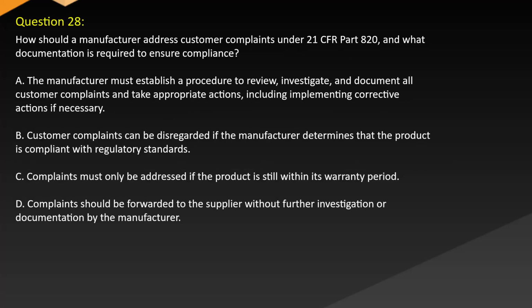Question 28. How should a manufacturer address customer complaints under 21 CFR Part 820, and what documentation is required to ensure compliance? A. The manufacturer must establish a procedure to review, investigate, and document all customer complaints and take appropriate actions, including implementing corrective actions if necessary. B. Customer complaints can be disregarded if the manufacturer determines that the product is compliant with regulatory standards. C. Complaints must only be addressed if the product is still within its warranty period. D. Complaints should be forwarded to the supplier without further investigation or documentation by the manufacturer.